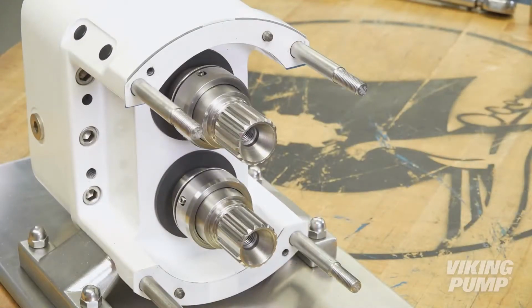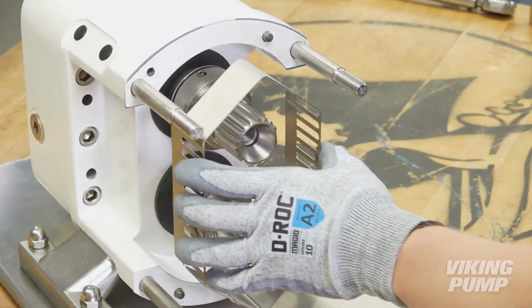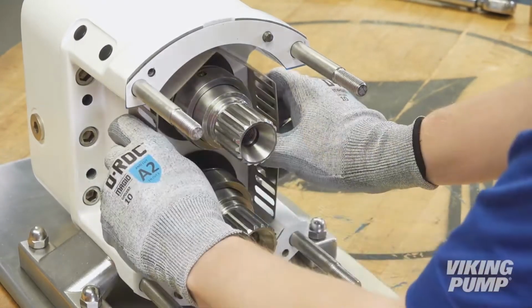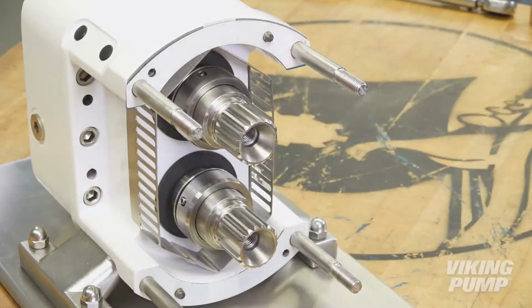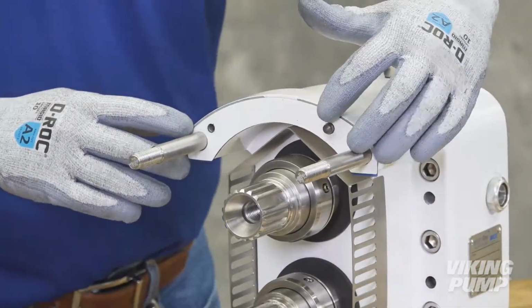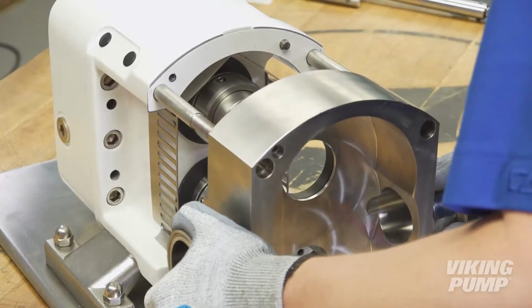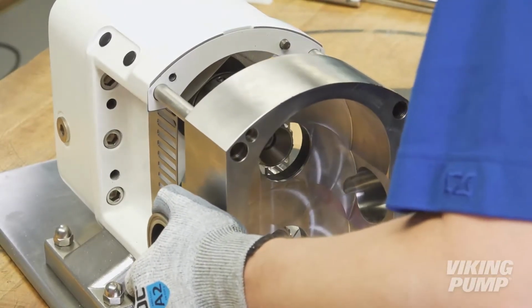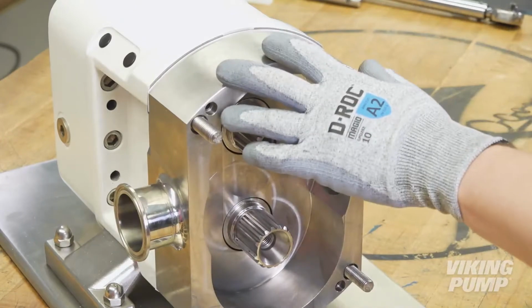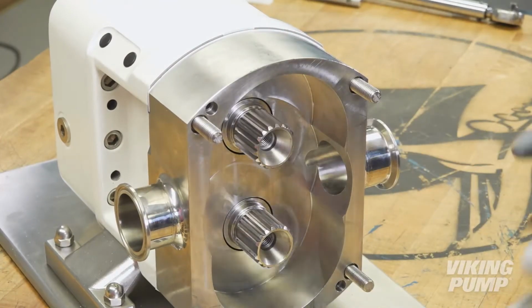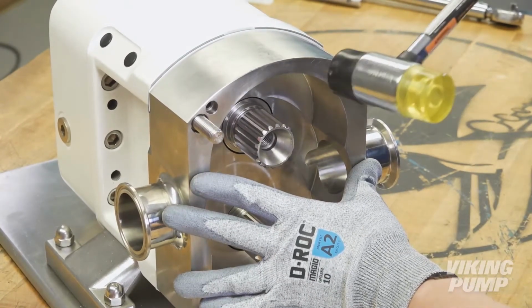Torque the set screws evenly according to the service manual. You may now reassemble the pump. First, reinstall the guard. Reinstall the shims, if removed, and the rotor case to the bearing housing. Make sure the same shim thicknesses are used and the casing is back in its original orientation. A soft-headed hammer may be required to seat the casing on the dowels.